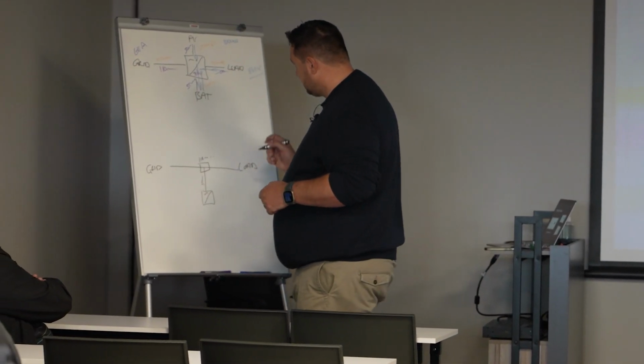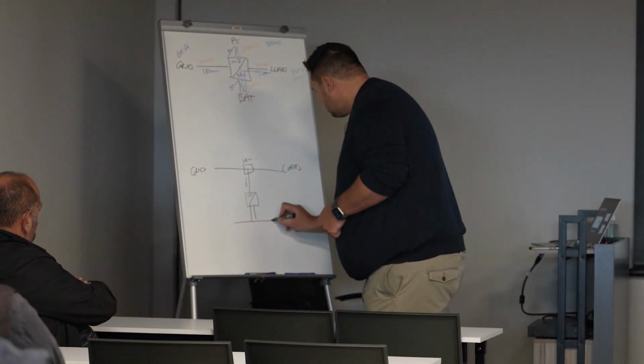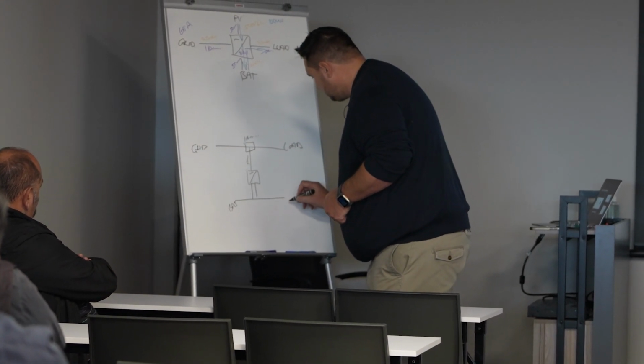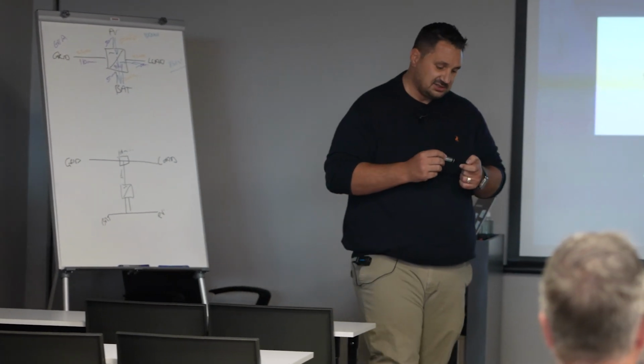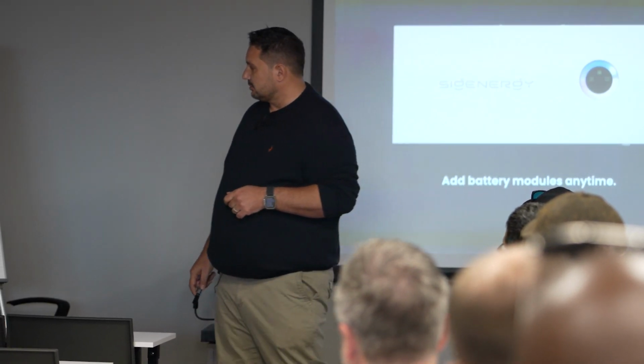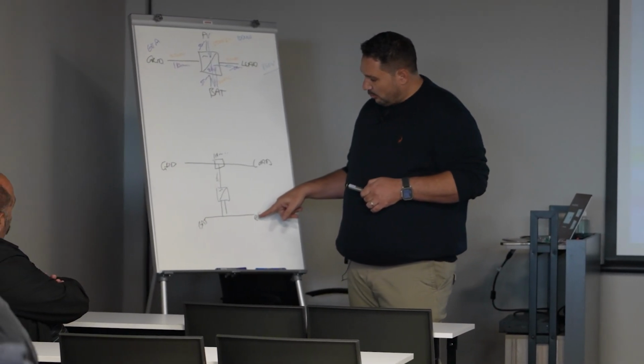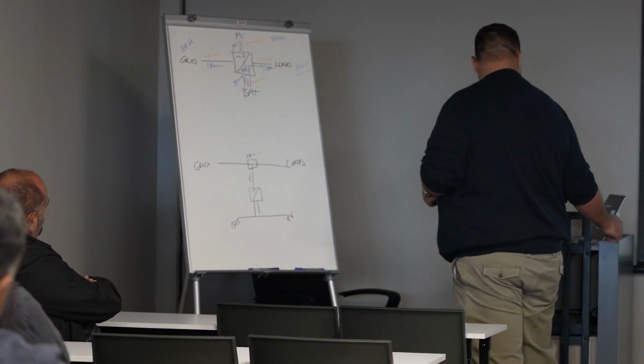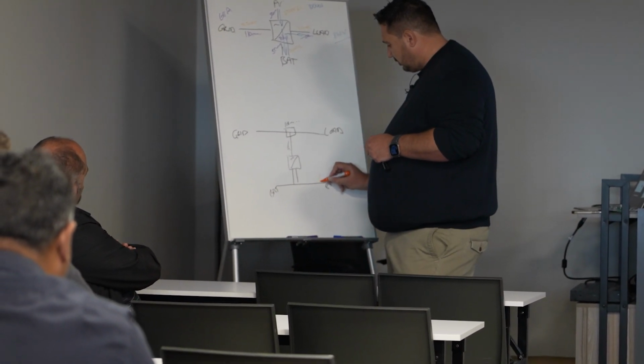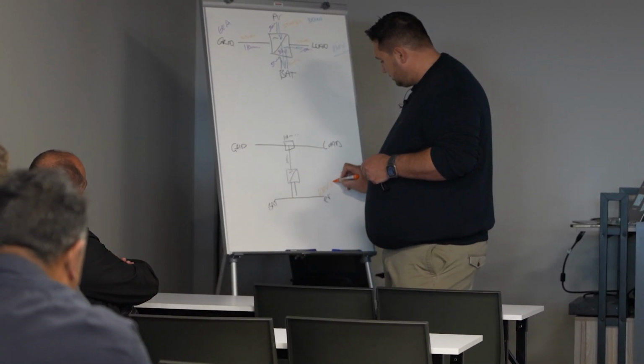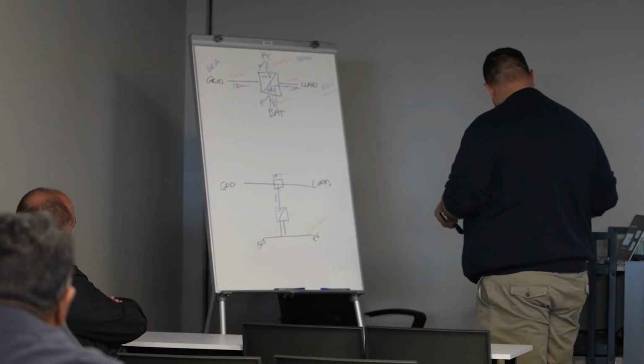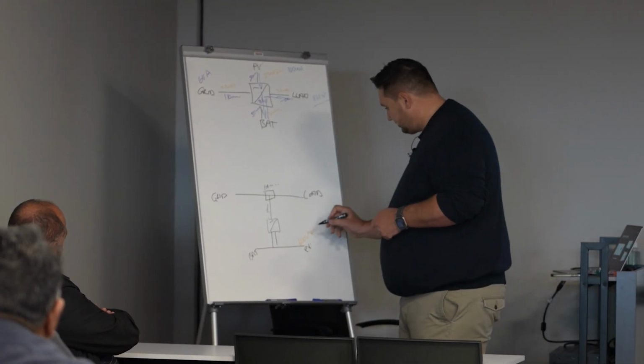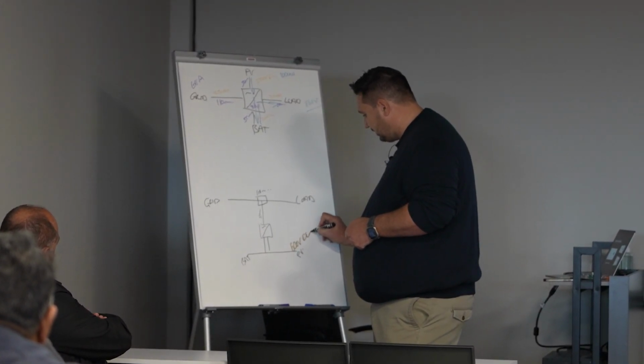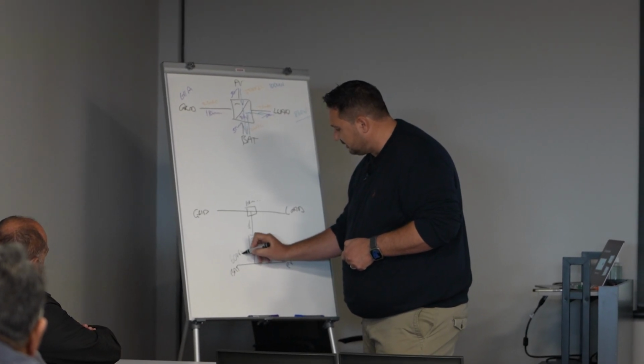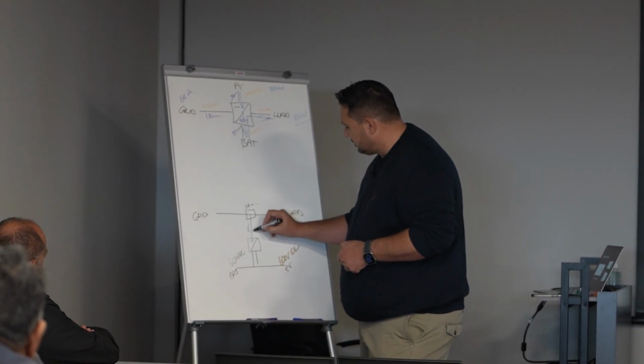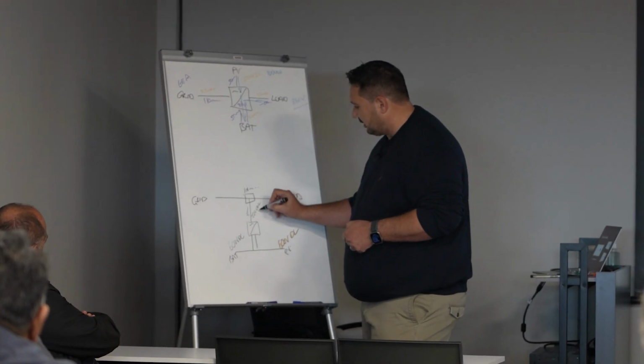But here's the other magic. What looks like here is there is your battery and there is your PV, and they are on the same DC bus. So now we have voltages. Let's go back to the orange one. 600 volts here, DC. Is that bad? Okay. Let's do black. We've got 600 volts DC over here. We've got 600 volts DC over here. We've got 220 AC over here.